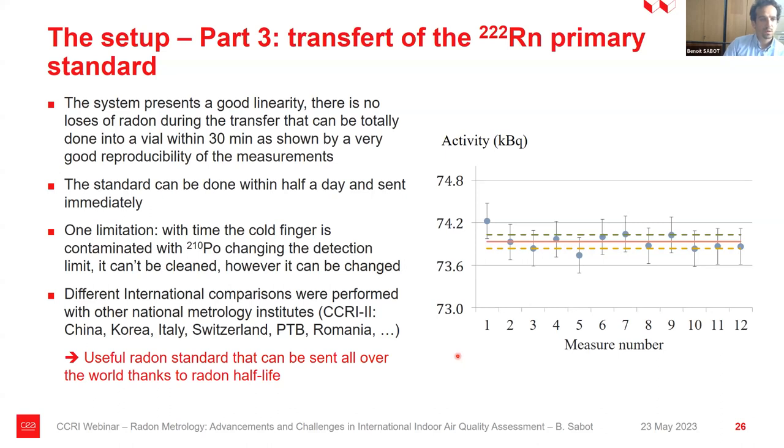However, there is one limitation with this system. Even though you need just half a day, let's say, to prepare a standard, when you use it a lot, with time you will see that polonium 210 is growing on the cold finger. When you measure very high activity of radon and repeat this for many years, the decay products will accumulate on the cold finger surface, but it's a solid while the radon is a gas. And thus we'll have polonium 210 that will come with time.